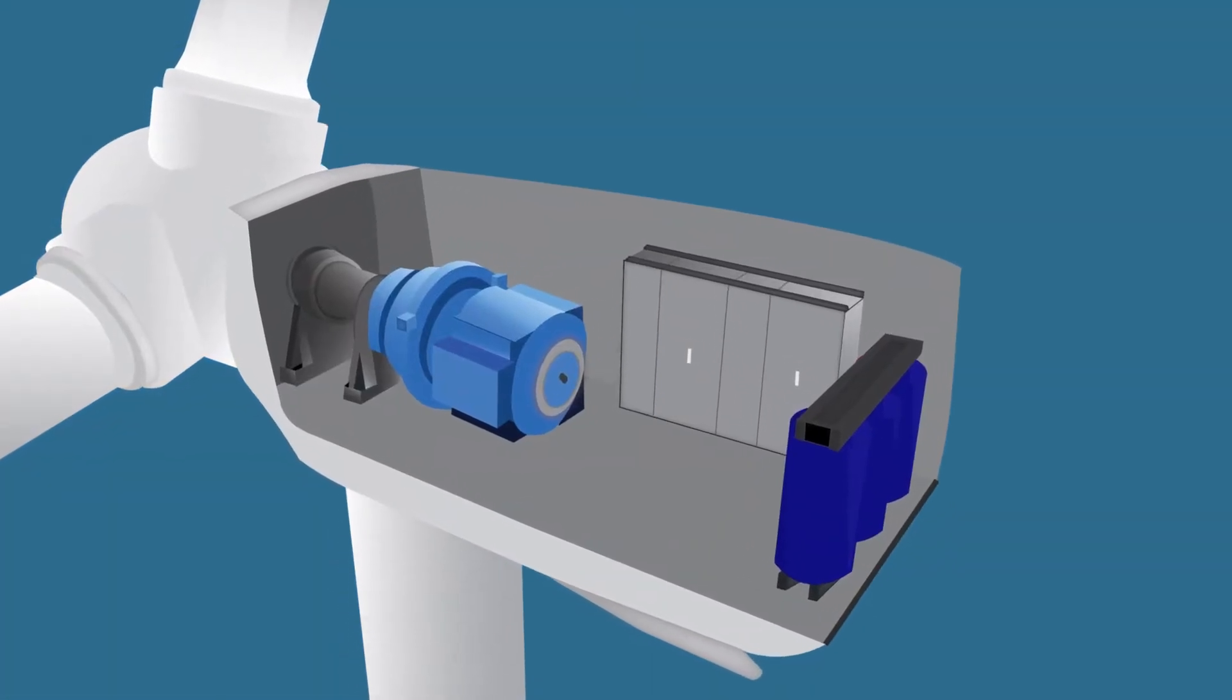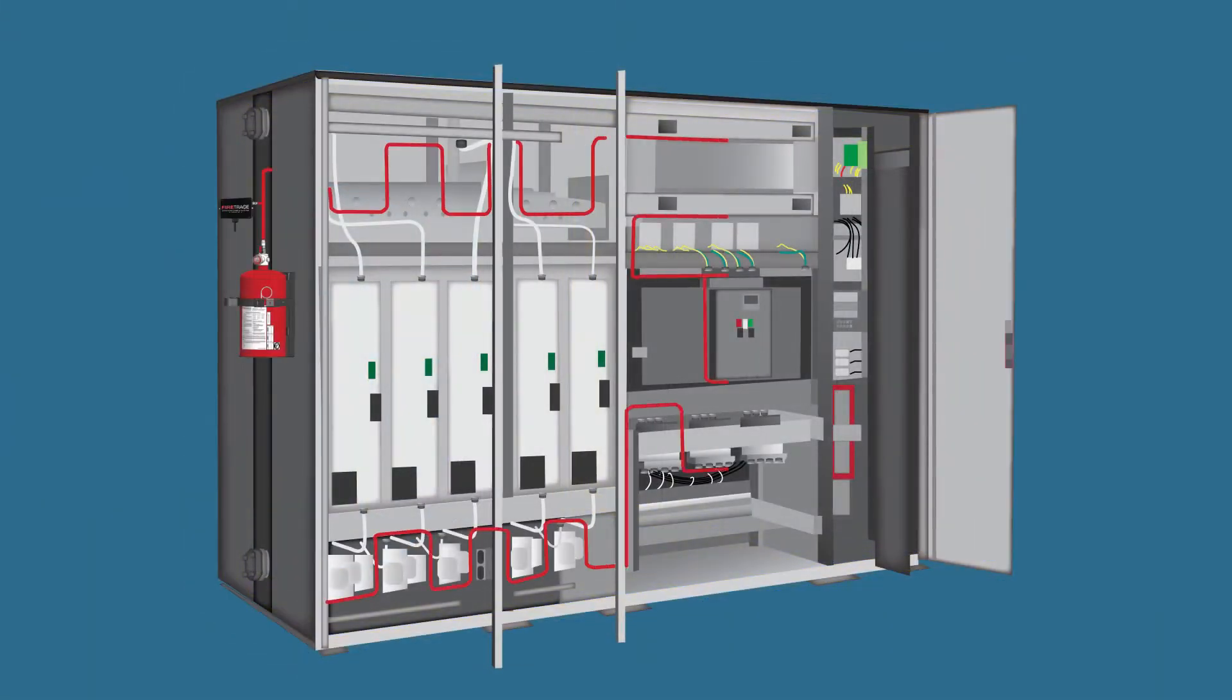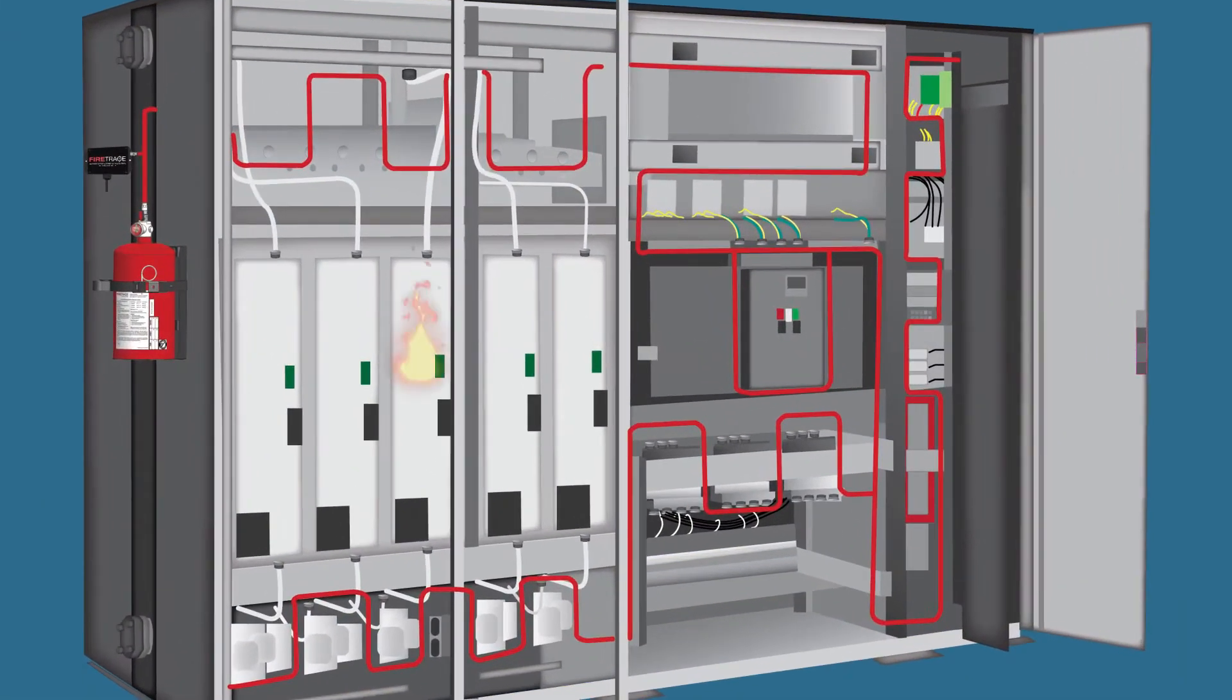The FireTrace detection tubing is installed throughout the area you are protecting. If fire or high ambient heat is detected, the detection tubing bursts at the source and releases the suppression agent directly at the fire.